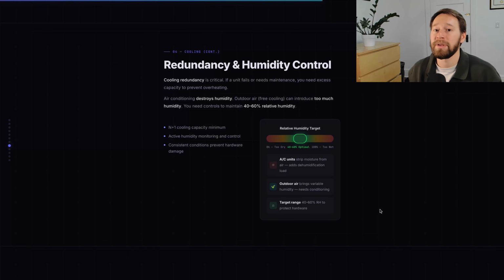You still need two units, because if one fails, you can't operate with no air conditioning. Maybe you can, but you're putting your SLAs at risk. So my recommendation would be to get many smaller systems. You can find the math online for how many tons of air conditioning you need for how many kilowatts of power going through computer systems. You want to size it so you've got very granular control. Maybe you've got 20 different air conditioners servicing different areas, but in every area there are multiple air handlers and condensers servicing that same spot, so if any component fails, it's fine because there's still plenty of air conditioning going in. That's how the redundancy works.